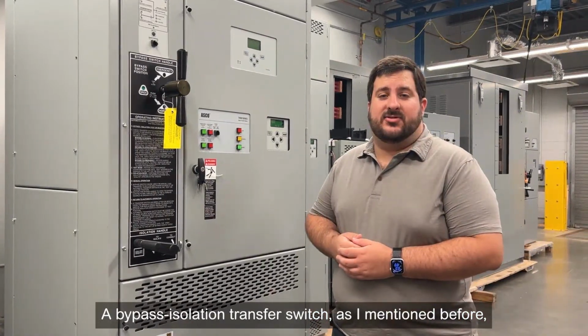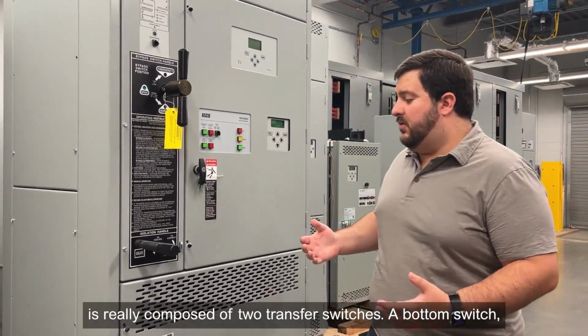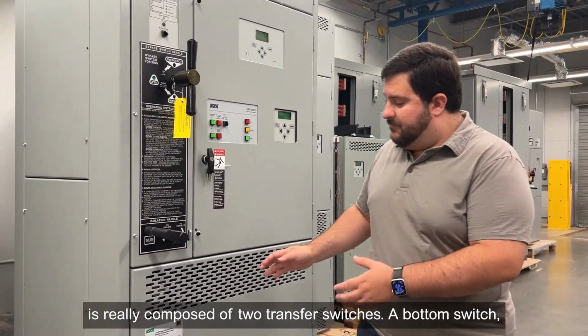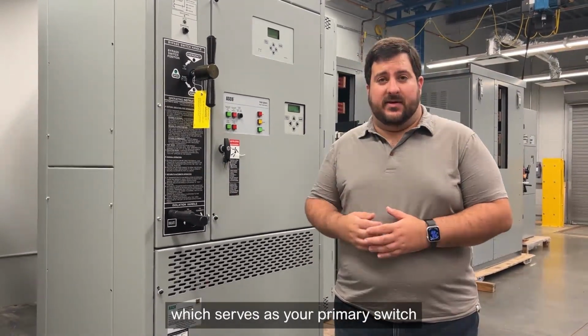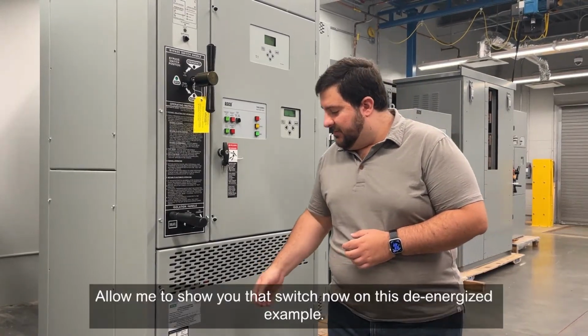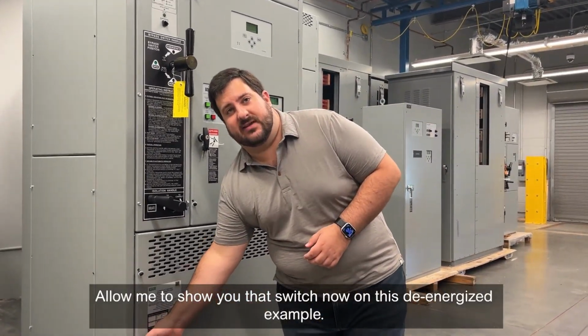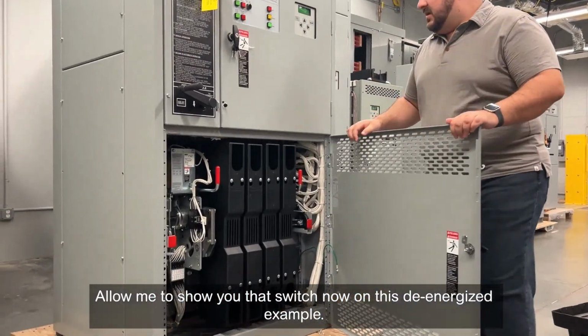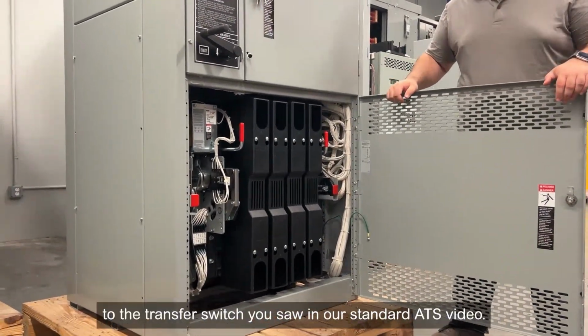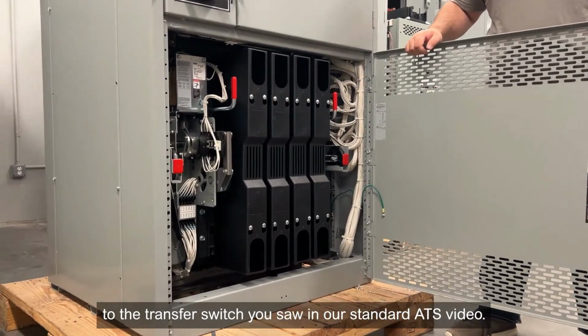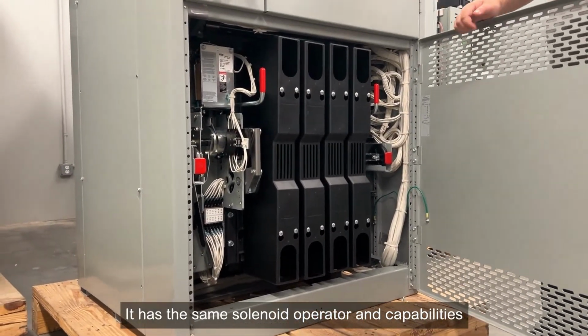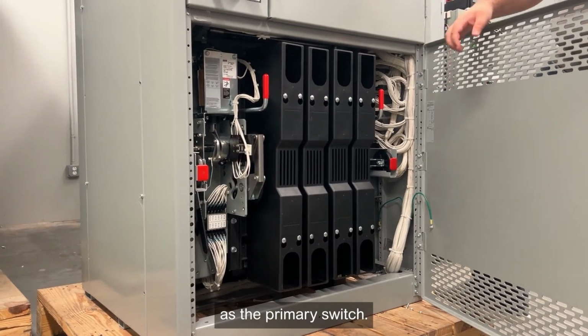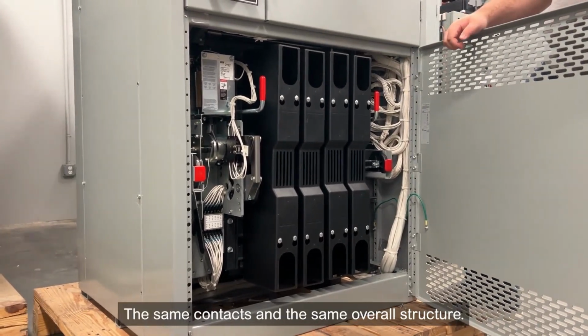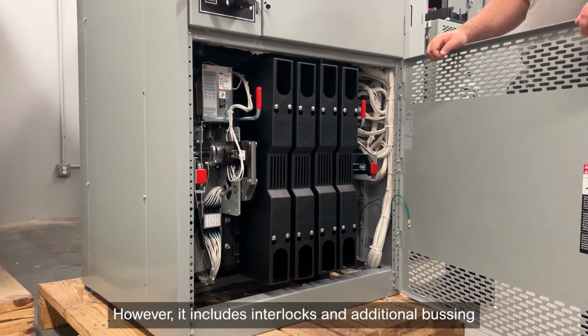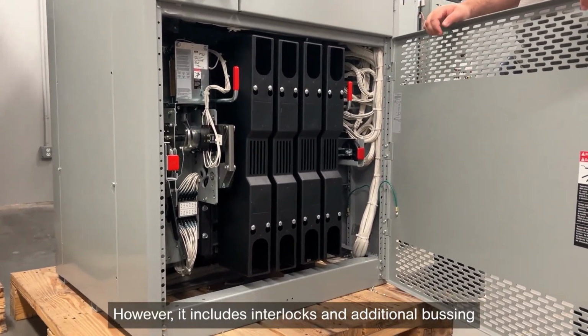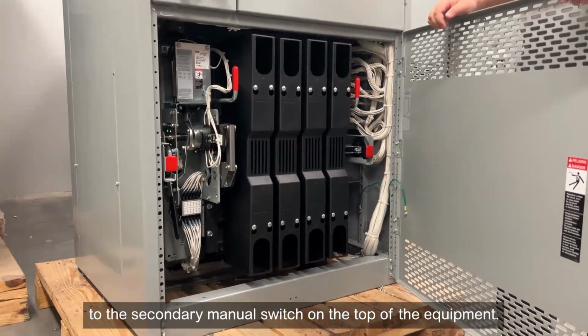A bypass isolation transfer switch, as I mentioned before, is really composed of two transfer switches. A bottom switch, which serves as your primary switch and is operating most of the time. Allow me to show you that switch now on this de-energized example. The bottom switch is very similar to the transfer switch you saw in our standard ATS video. It has the same solenoid operator and capabilities as the primary switch, the same contacts, and the same overall structure. However, it includes interlocks and additional busing that connects it to the secondary manual switch on the top of the equipment.